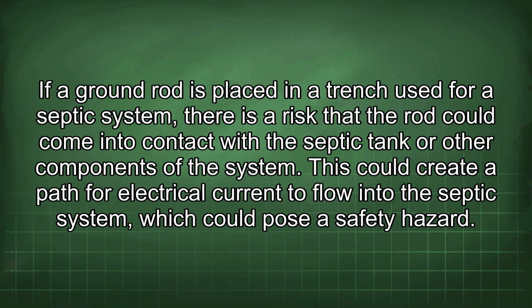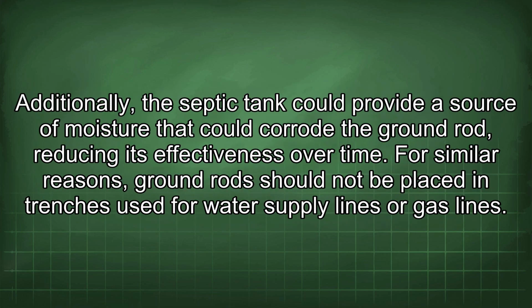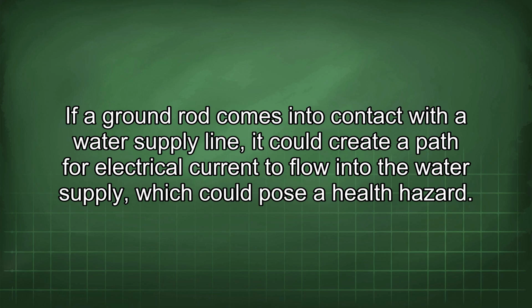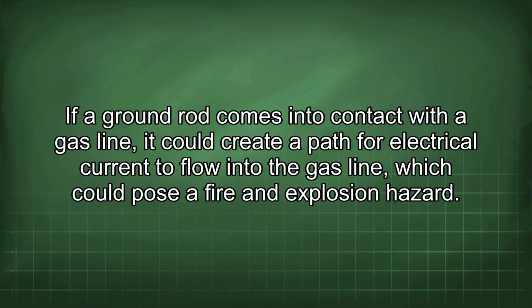This could create a path for electrical current to flow into the septic system, which could pose a safety hazard. Additionally, the septic tank could provide a source of moisture that could corrode the ground rod, reducing its effectiveness over time. For similar reasons, ground rods should not be placed in trenches used for water supply lines or gas lines. If a ground rod comes into contact with a water supply line, it could create a path for electrical current to flow into the water supply, which could pose a health hazard. If a ground rod comes into contact with a gas line, it could create a path for electrical current to flow into the gas line, which could pose a fire and explosion hazard.